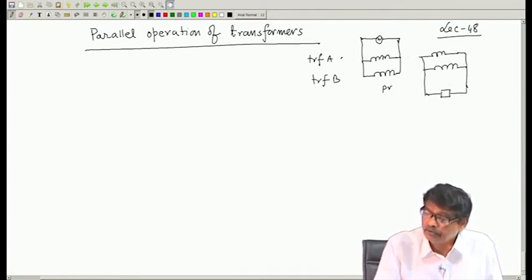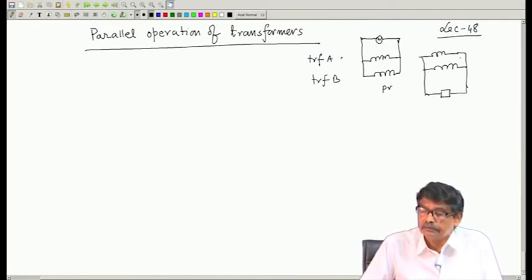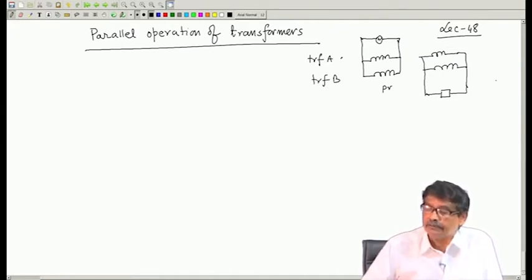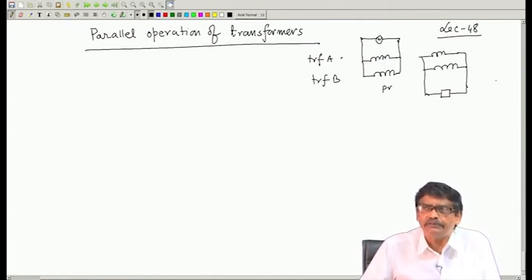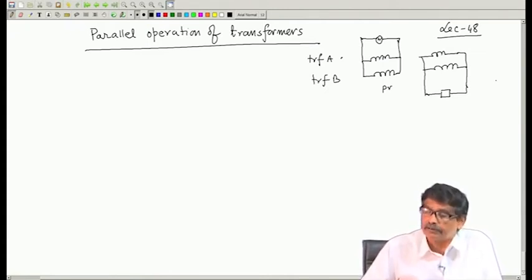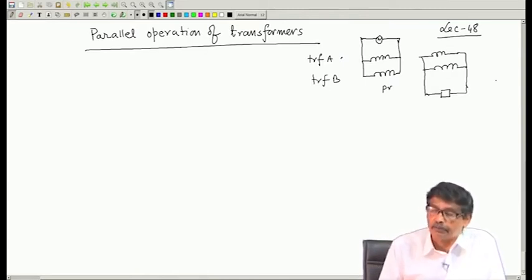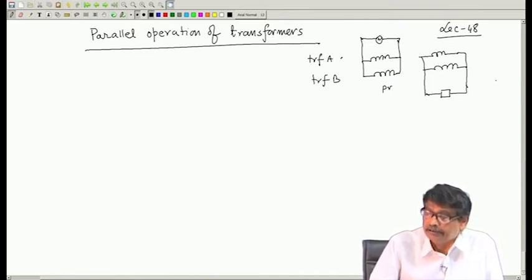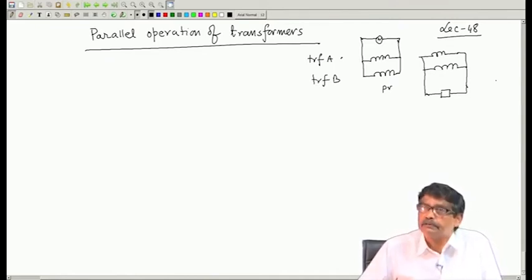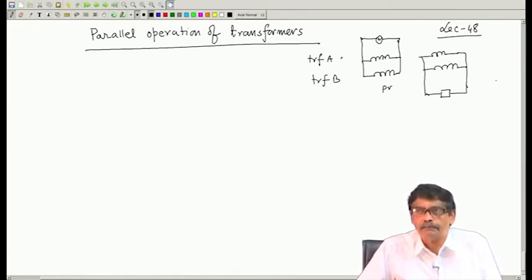Got the point? So, two transformers. Similarly, if it is more than 2, another primary will come in parallel, and another secondary of transformer C. A and B have nothing to do with A phase and B phase, just naming the transformers. So, let us first discuss this single phase operation. This is what is meant by parallel connection: you connect the primaries in parallel, also the secondaries in parallel to supply the load, and the primaries are supplied with a source.